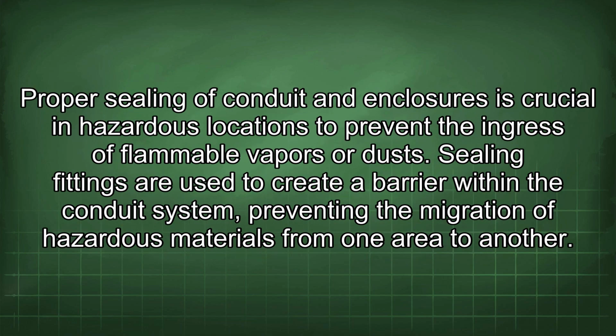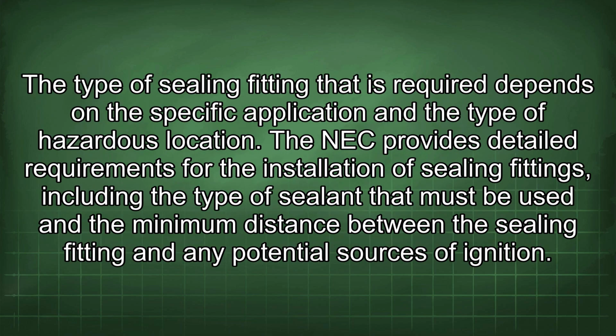Proper sealing of conduit and enclosures is crucial in hazardous locations to prevent the ingress of flammable vapors or dusts. Sealing fittings are used to create a barrier within the conduit system, preventing the migration of hazardous materials from one area to another. The type of sealing fitting that is required depends on the specific application and the type of hazardous location. The NEC provides detailed requirements for the installation of sealing fittings, including the type of sealant that must be used and the minimum distance between the sealing fitting and any potential sources of ignition.